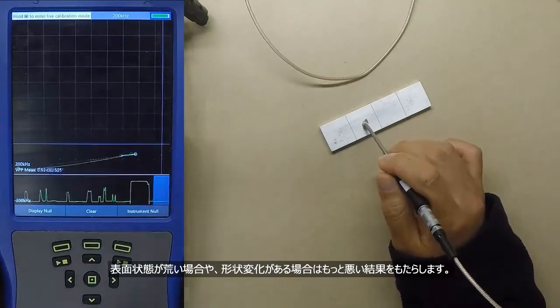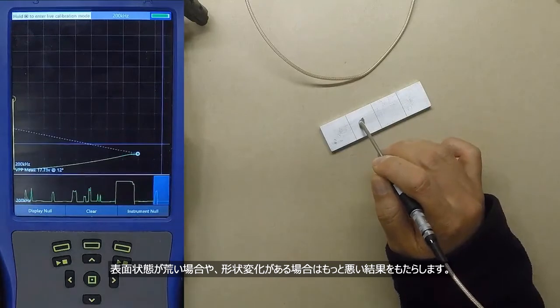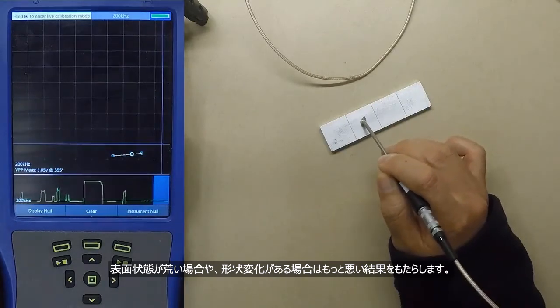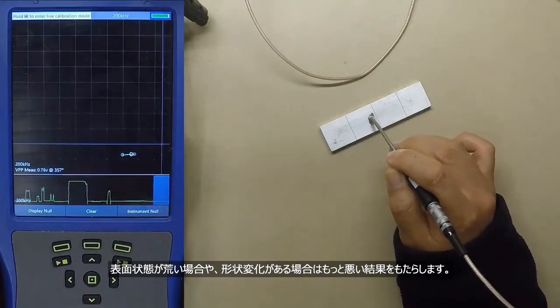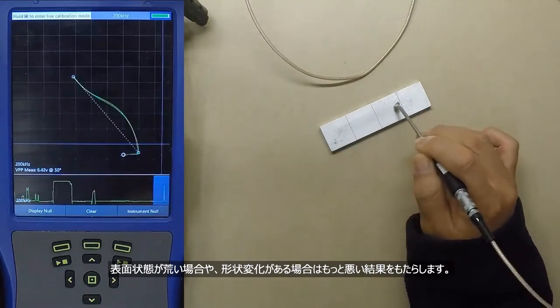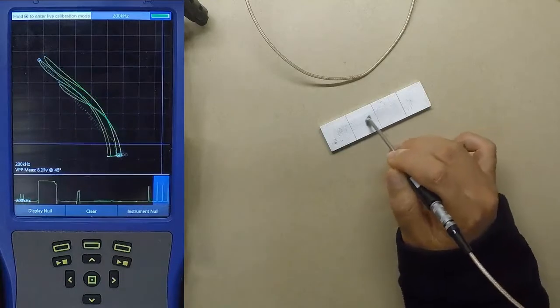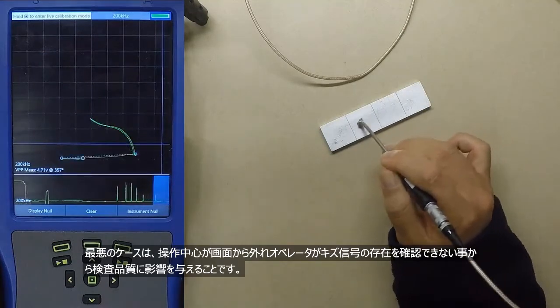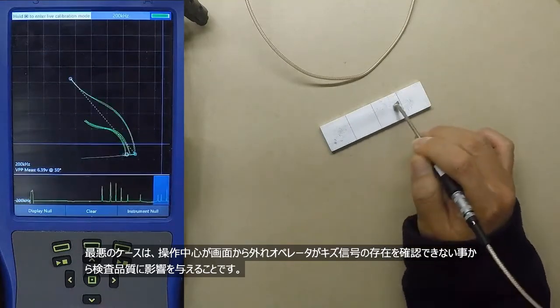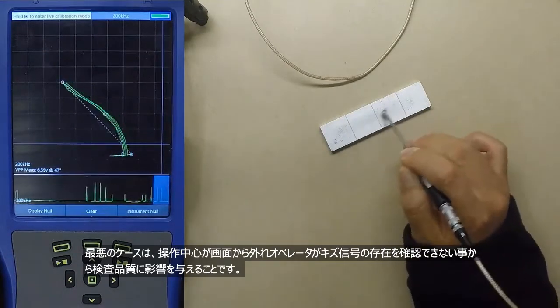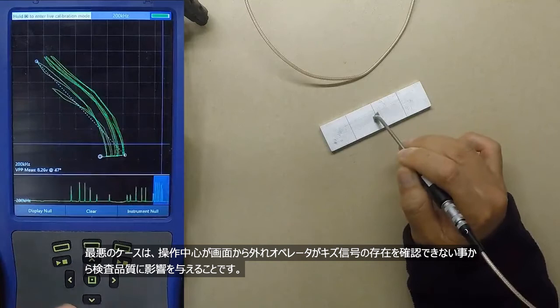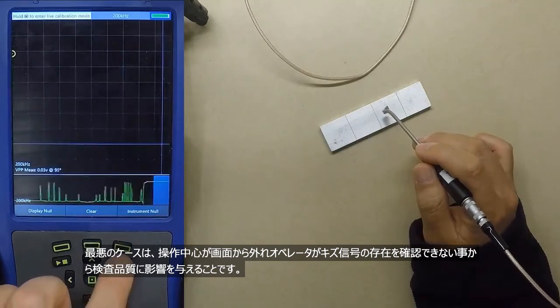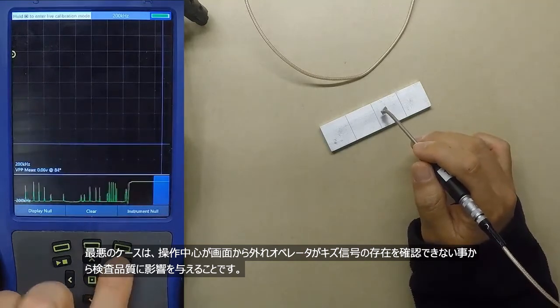This gets much worse if you have a surface which is not smooth or has different geometries. At worst, POD can be affected if the operating point moves off the screen and the inspector is unable to identify flaw signals.